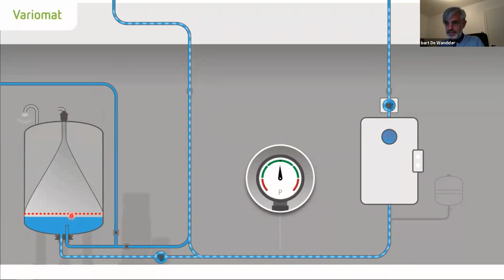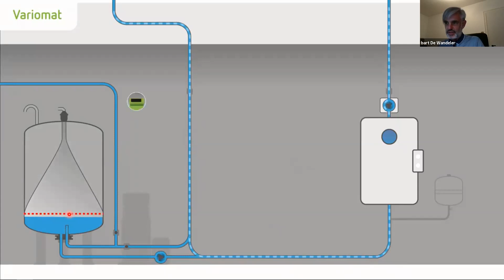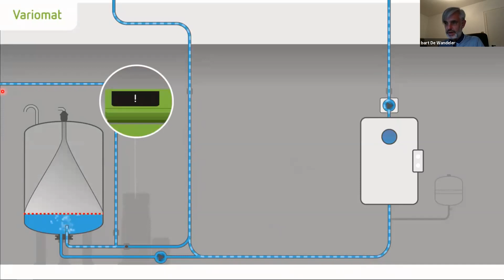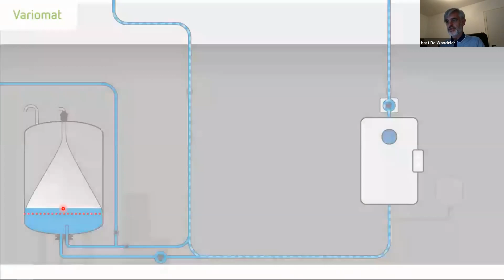Of course, when we degas, like I have mentioned, we can go to a critical water reserve. This is dangerous. This is the problem that we have often with static vessels. We degas and we do not have enough water reserve. We get an alarm. We will open the water makeup line and we will again provide the suitable water reserve for the pressurization system.